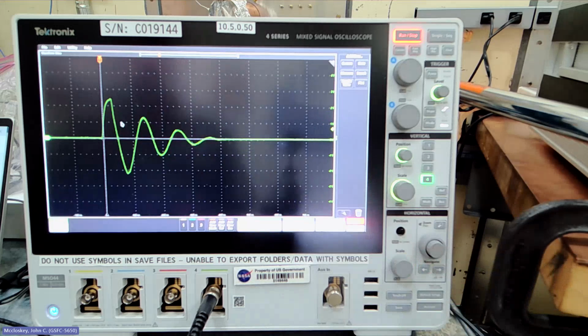But the pre-calibration into the test fixture is an extremely important step so that you know what it is you're injecting into a controlled impedance. And then when you go to your cable under test, you inject that pre-calibrated level, and the resulting waveform just is what it is, and you record it. You record the waveform that you injected into the test fixture and put that in your test report, and then you record this waveform at as many different time bases and amplitude scales as you want to get a good fidelity on the signal, and say, okay, this is what we got into the cable under test.